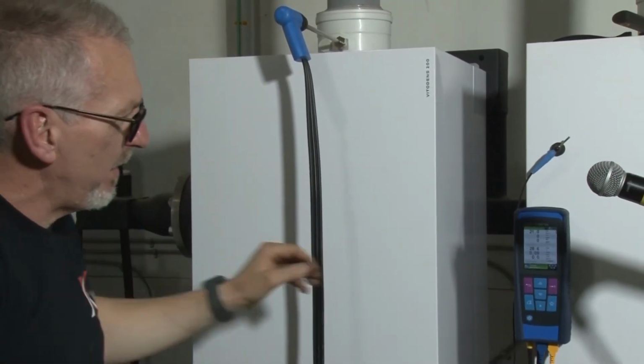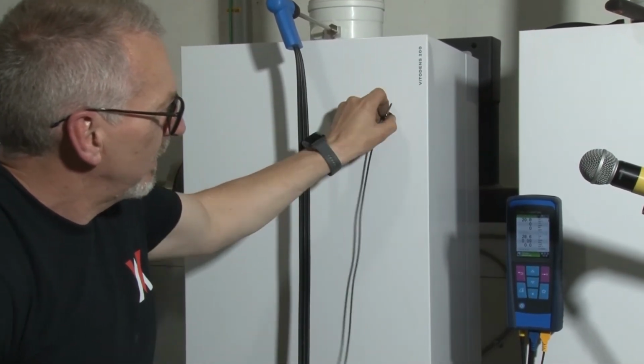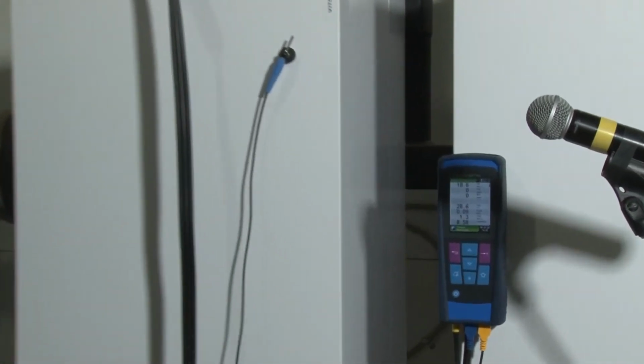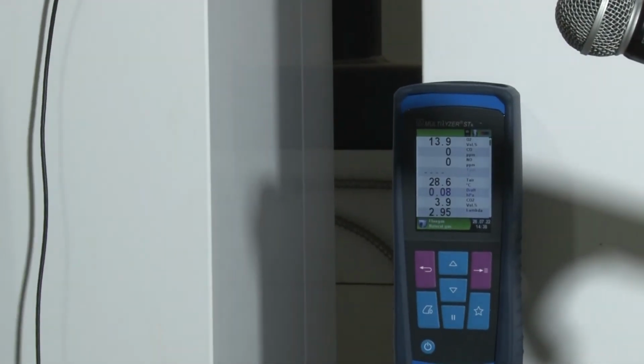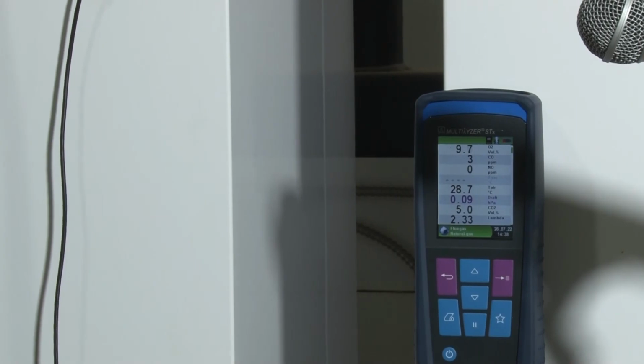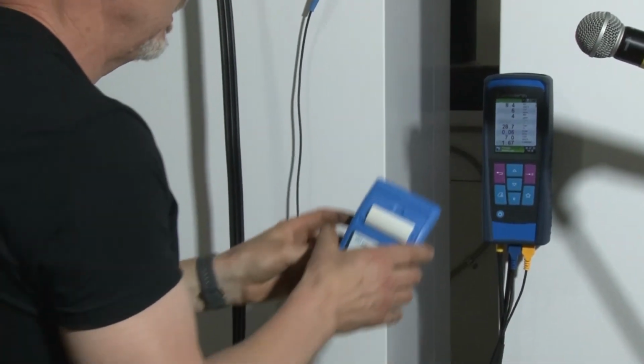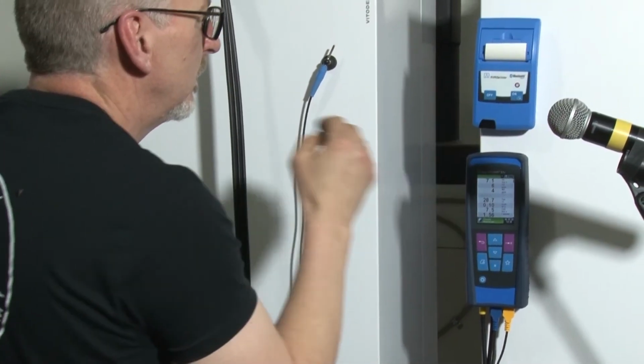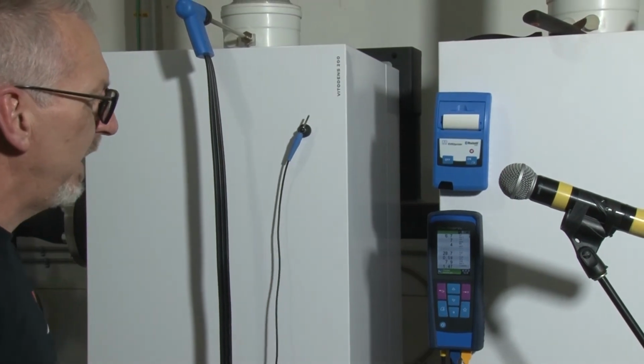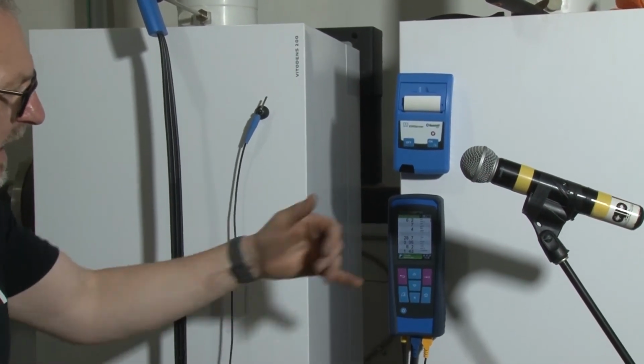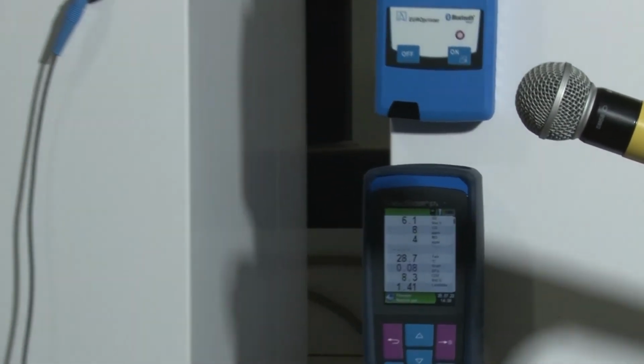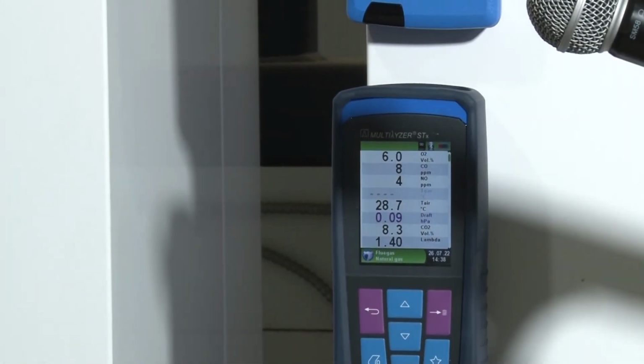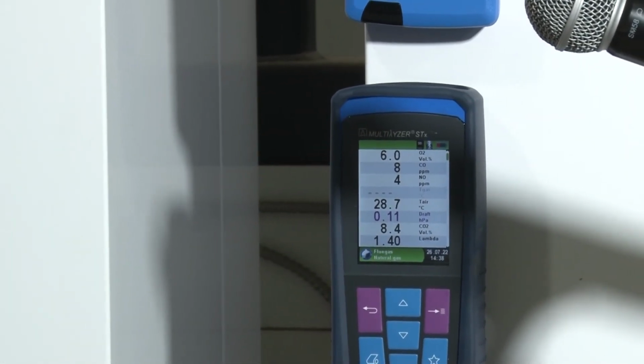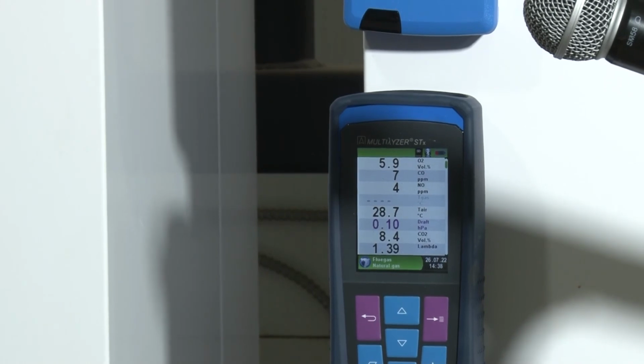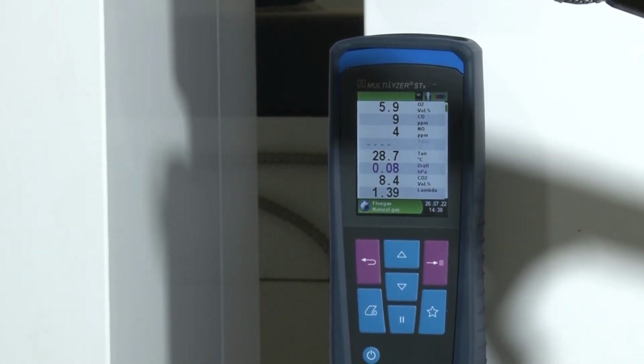And basically from here, we're just starting to have a look at what the numbers look like on the screen. And with this particular analyzer, you've also got the little printer. So if you want to take a measurement here, we got to let it stabilize a little bit. So pump is running. If we don't have a load, obviously it might heat up a little quicker than what we're looking for, but the idea is that we're going to capture the low fire and then we're going to drive it to high fire.